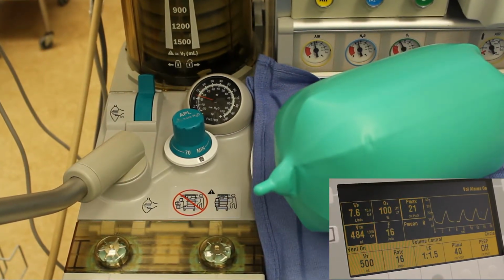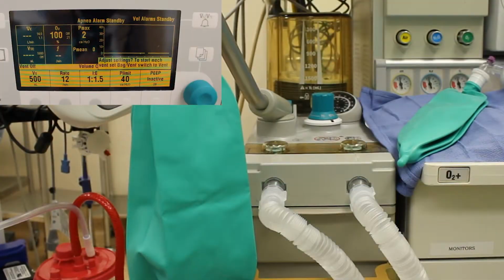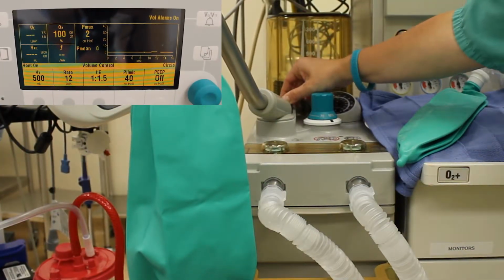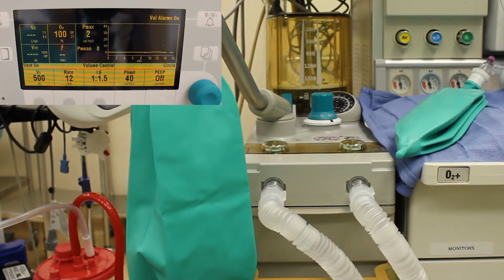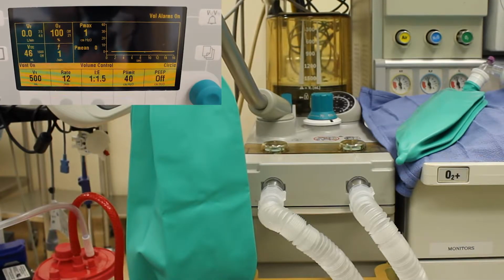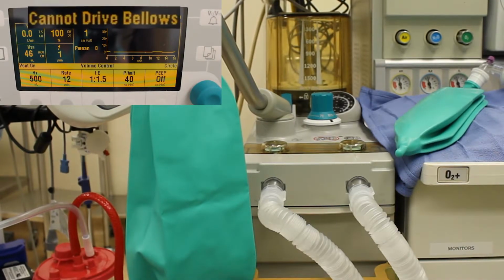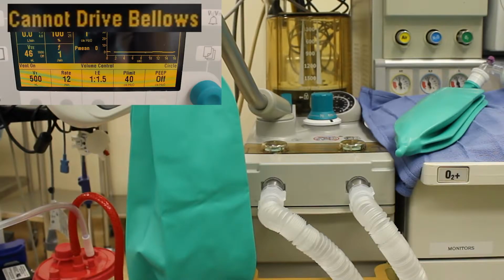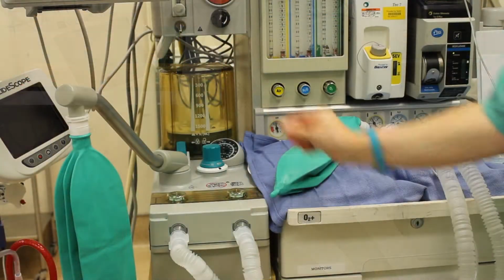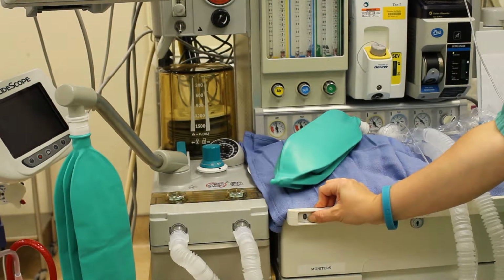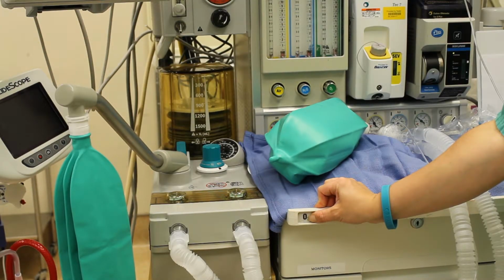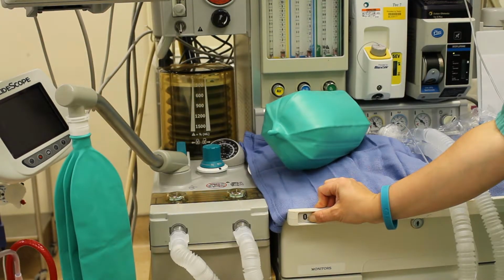Ascending bellows ventilators, as used in the Aestiva and Avance, must be filled before they can ventilate the patient. The ventilator is filled when the bellows reaches the top. Disconnecting the circuit from the patient with the ventilator still switched on will cause the bellows to empty. The O2 flush valve can be used to quickly fill the bellows, but not while the patient is connected, as this may lead to barotrauma.